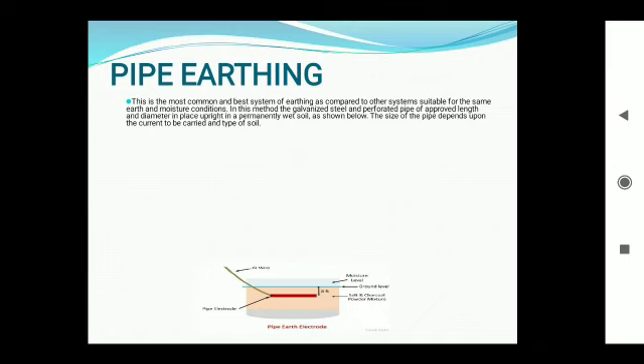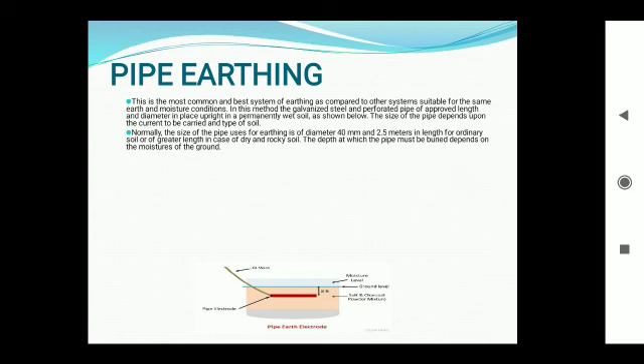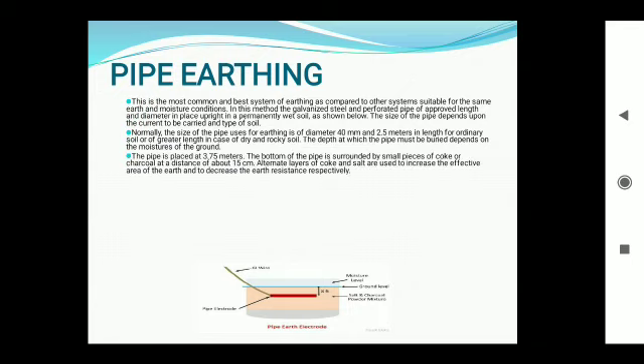The size of the pipe depends upon the current to be carried and type of soil. Okay, it means when the current is increased, the size of the pipe is also increased. Normally, the size of the pipe used for earthing is of diameter 40 mm and 2.5 meter in length for ordinary soil. The pipe is placed at 3.75 meter. The bottom of the pipe is surrounded by small pieces of coke and charcoal to reduce the earth resistance. And alternate layers of coke and salt are used to increase the effective area of the earth and to decrease the earth resistance respectively. It means it also increases the earth conductivity.